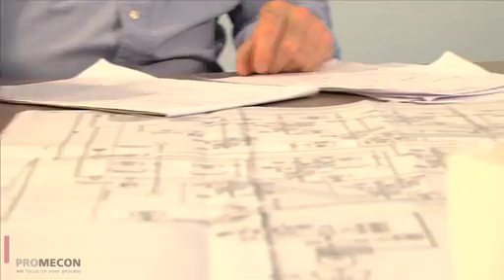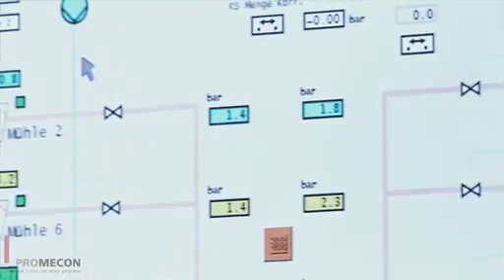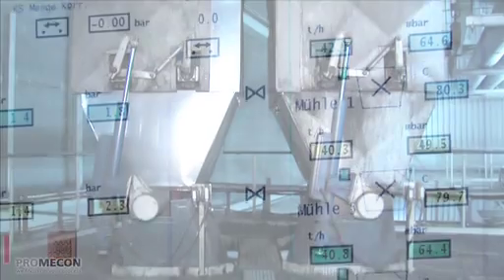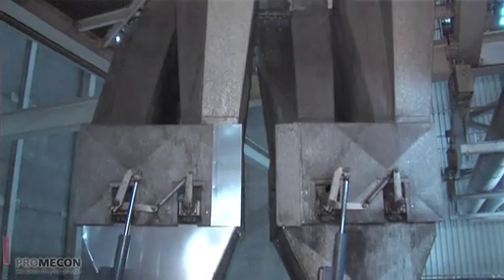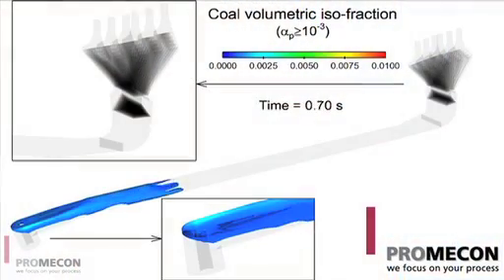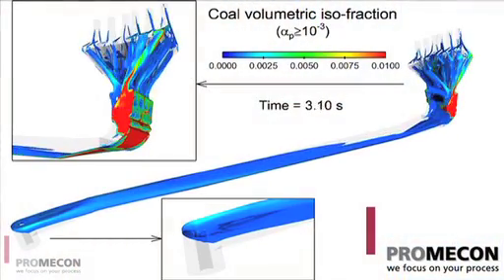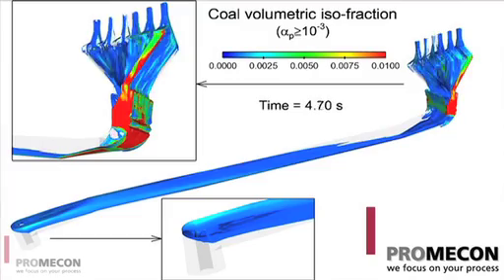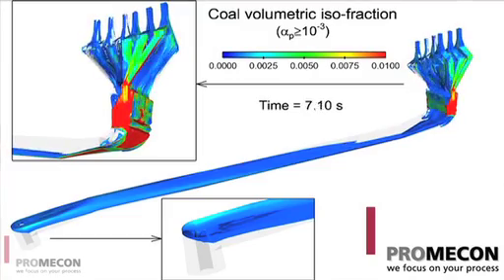Certainly the mass flow, because that's perhaps the dominant input. Do we really know what we put into the mill in terms of fuel-air? Do we really know what we take out? And do we know that what we take out is uniformly distributed to each of the burners? If we can establish uniformity from burner to burner, we could then seriously think about matching mill to mill. And if at the same time we could maintain a minimum velocity in the pipes such that we didn't get fallback product and we don't have it lying like sand dunes in the pipes, then we'd be on our way to getting something like optimum efficiency.